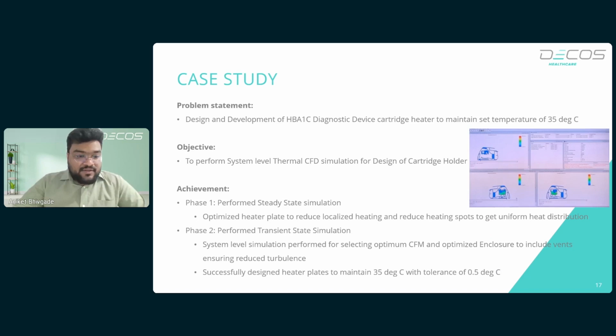Once that was done, we performed the transient simulation over the complete system, where we chose an optimal CFM. But once we chose a CFM, some turbulence issues happened, so we suggested adding vents to the enclosure, and that's how we successfully maintained 35 degrees Celsius in the enclosure by designing the heater plate and modifying the enclosure.